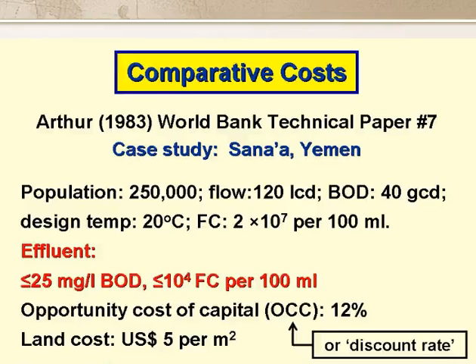We are now going to look at a case study developed by Jim Arthur for the World Bank in the early 1980s. He compared four different wastewater treatment processes to treat the wastewater from the city of Sana'a in the Yemen Arab Republic. Arthur designed these systems for a population of 250,000, a wastewater flow of 120 litres per person per day, and a BOD contribution of 40 grams per person per day.